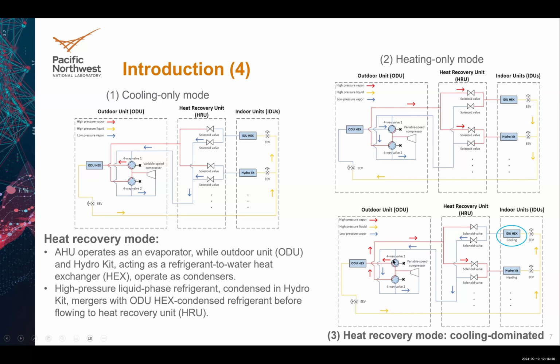If you look at the refrigerant flow, you have a compressor here that produces high temperature, high pressure refrigerant. This refrigerant will flow to one of the indoor terminals. Here it is the hydro kit. Then the refrigerant will be condensed into high temperature liquid. This liquid will merge with the other condensed refrigerant from the outdoor unit heat exchanger. Finally, this merged refrigerant flow will flow to the heat recovery unit, then lastly back to the suction side of the compressor.